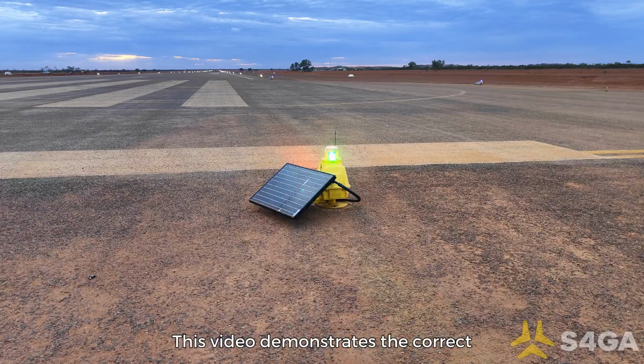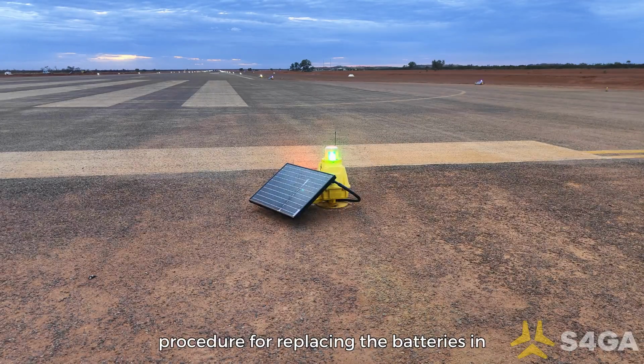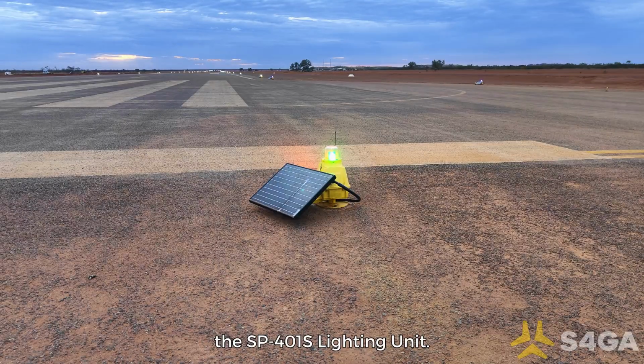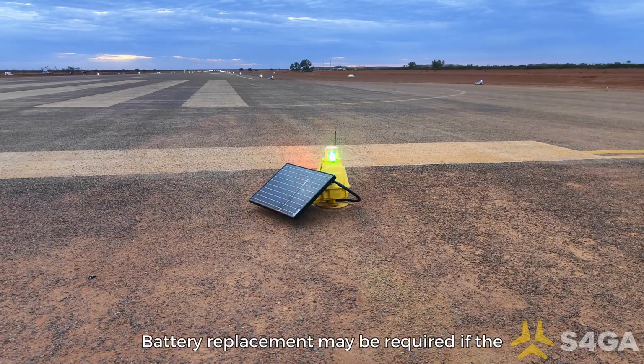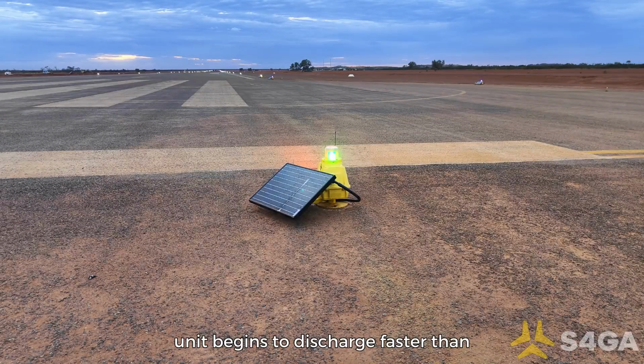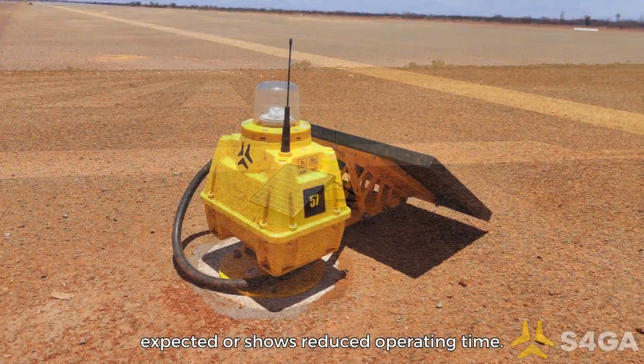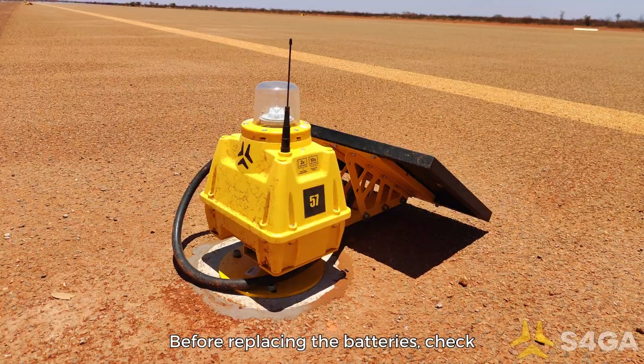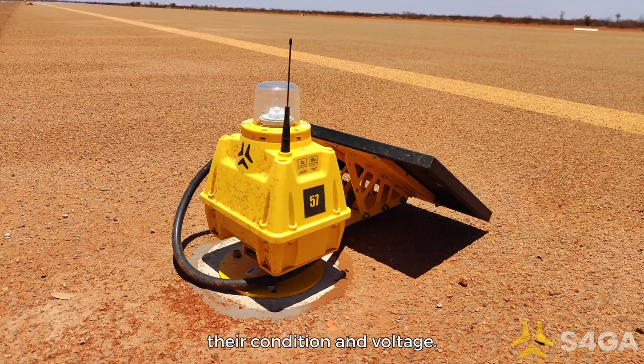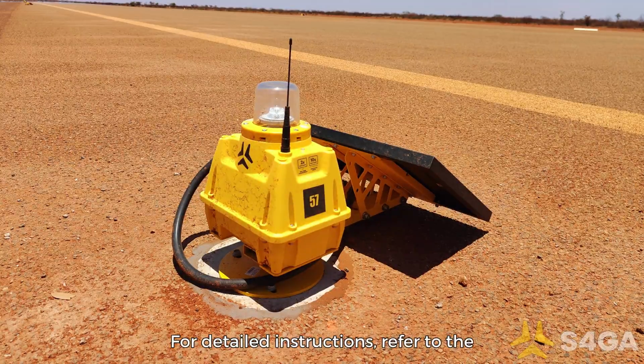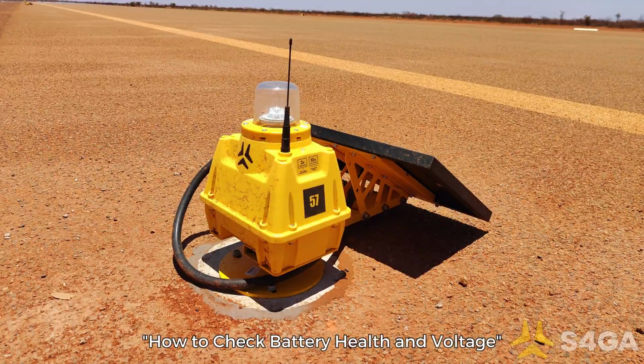This video demonstrates the correct procedure for replacing the batteries in the SP-401S lighting unit. Battery replacement may be required if the unit begins to discharge faster than expected or shows reduced operating time. Before replacing the batteries, check their condition and voltage. For detailed instructions, refer to the How to Check Battery Health and Voltage video.